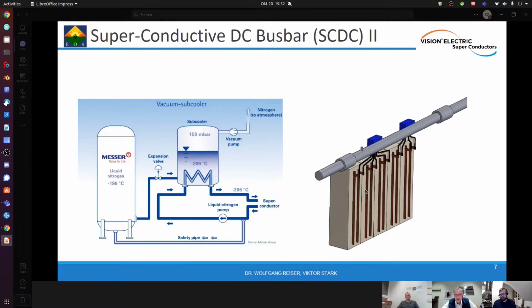And of course you need some protection device to be sure that nothing happens if a short circuit on the OCP rack occurs, so that it will not destroy or damage the busbar system. So there's a protection device on it. We also have a monitoring interface going to the central operating unit of the data center, to always show the system operator the situation of each of the OCP racks. So there is the system.